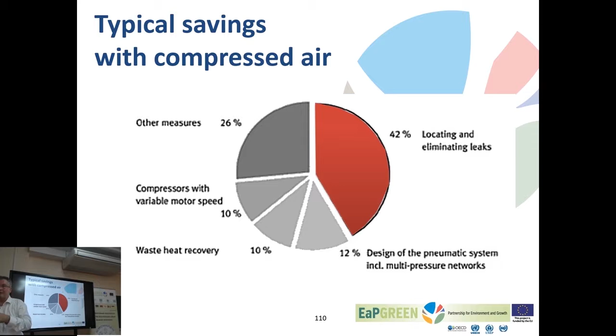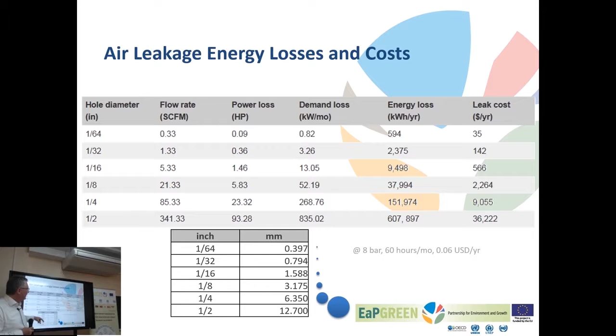This is the table then for your reference, what the diameter of a hole is, what the loss is, in this case calculated for 8 bars, and what the associated cost for energy is. Now for compressors, and we will discuss an analogous situation then for refrigeration compressors.